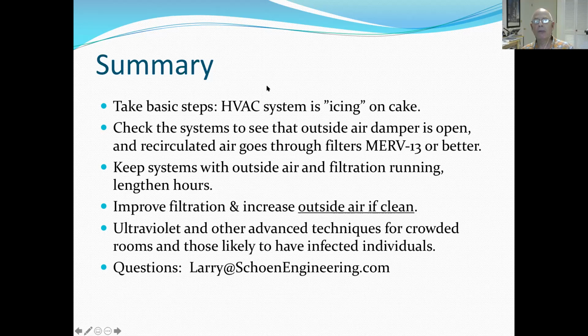Recommended air change rate for manufacturing plants. Even in the healthcare industry, they talk about air changes per hour for disease control, but I like to speak of CFM per person. Suppose you have a dense room of people; the air changes in the room don't really give you a clue for how that's being diluted per person.